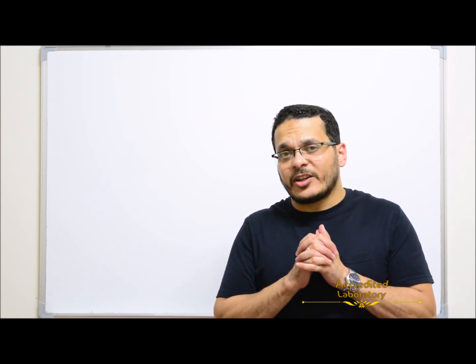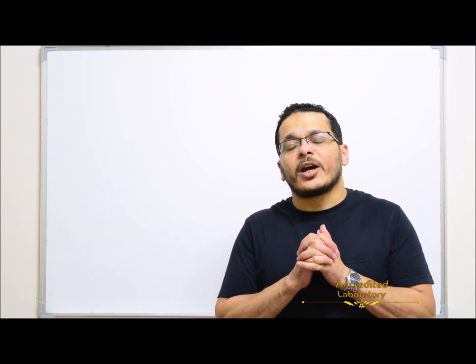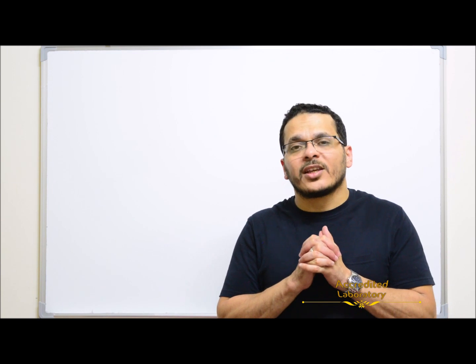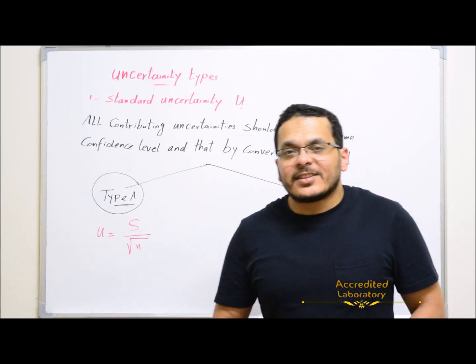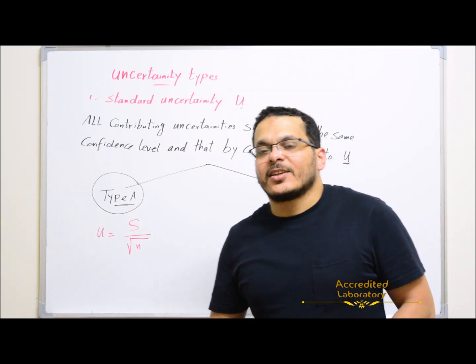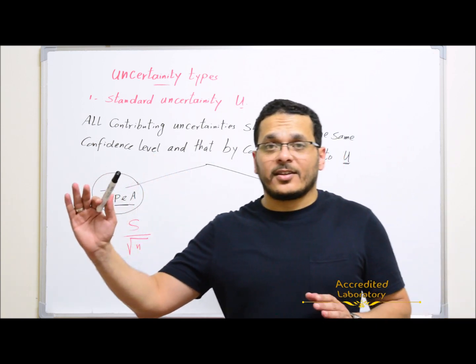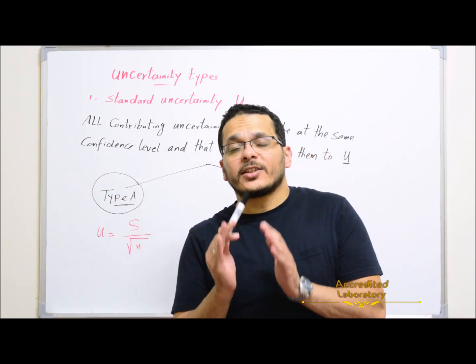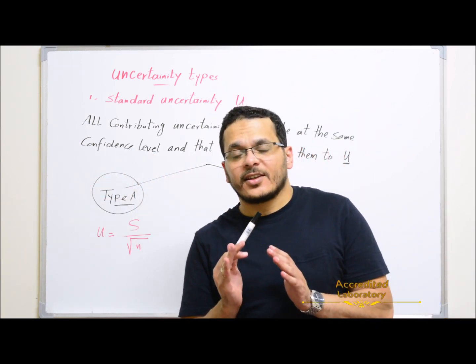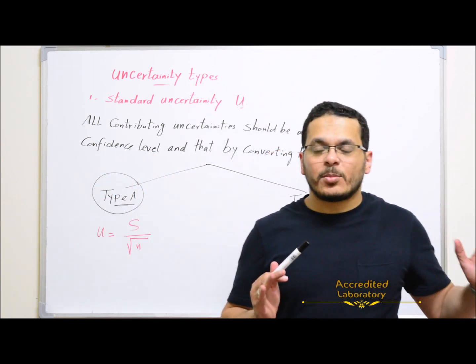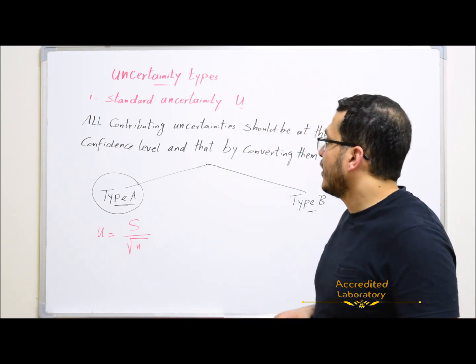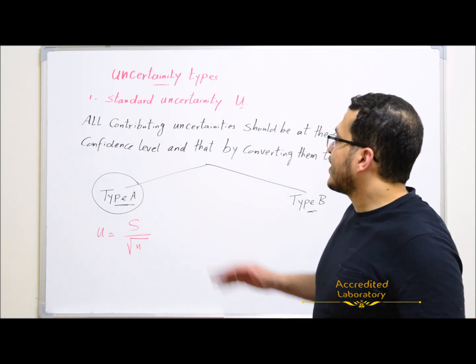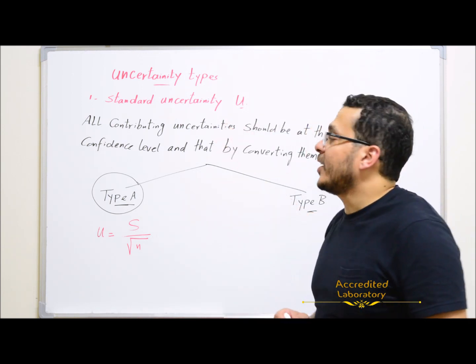Uncertainty from these two types of evaluation will be combined together to get overall uncertainty. There are three uncertainty types: standard uncertainty, combined uncertainty, and expanded uncertainty. Standard uncertainty is the standard deviation of the mean.